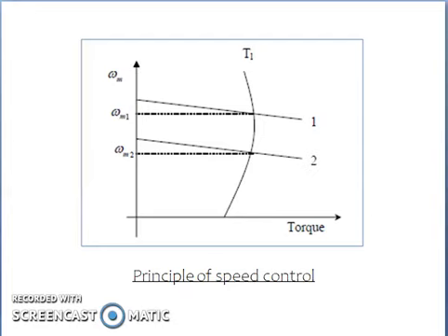In that, the motor is made to work as a generator and it converts mechanical energy to electrical energy, which produces torque in a direction opposing the motion. Even if we are using electrical braking, mechanical brakes may also be provided to ensure the reliable operation of the drive system.